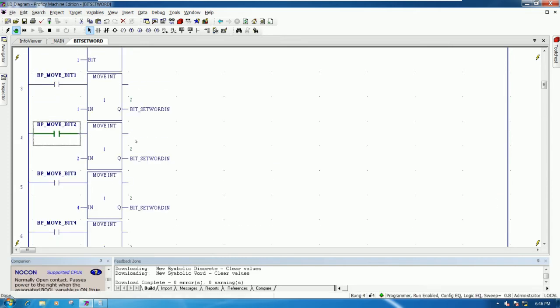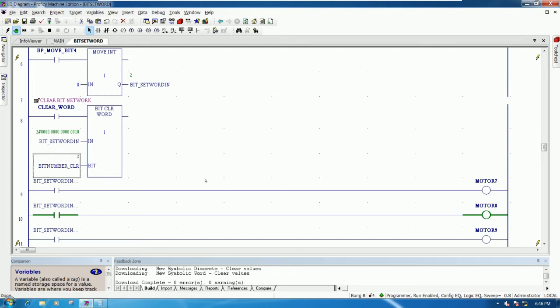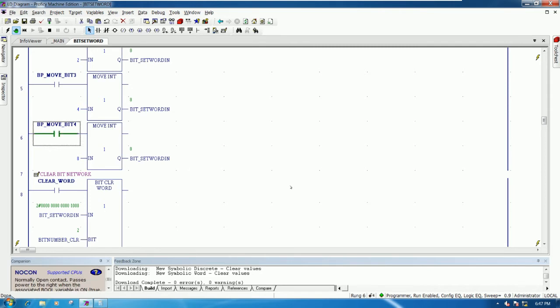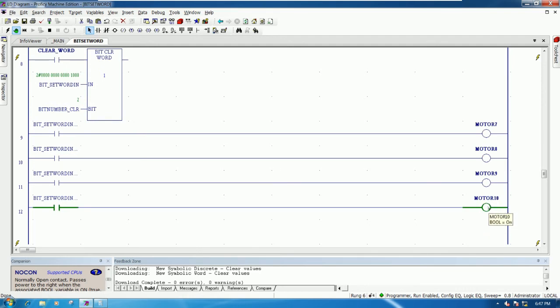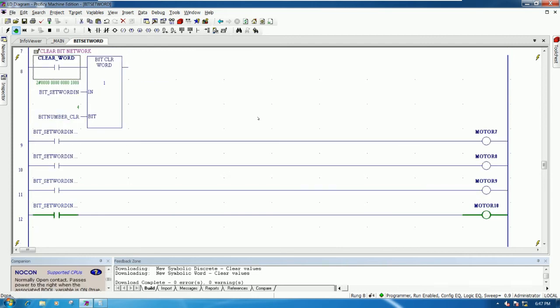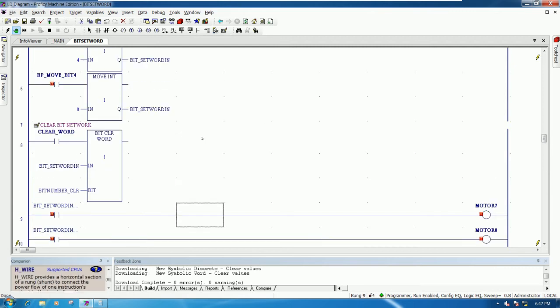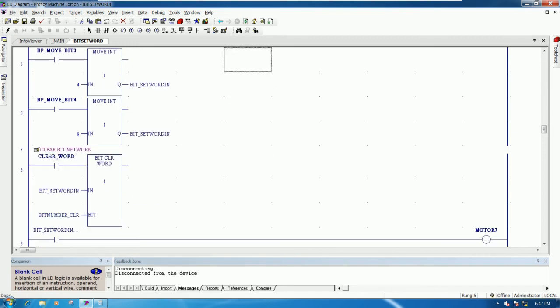If I want to clear, I will disable the enable first - the motor is still on - then I will write the number 2 to the clear variable and enable the clear to turn off the motor. If I start bit number four, the bit number four is turned on and motor number 10 is turned on. To clear, I choose value 4 and it will turn off. We can do this all the way up to bit number 16.